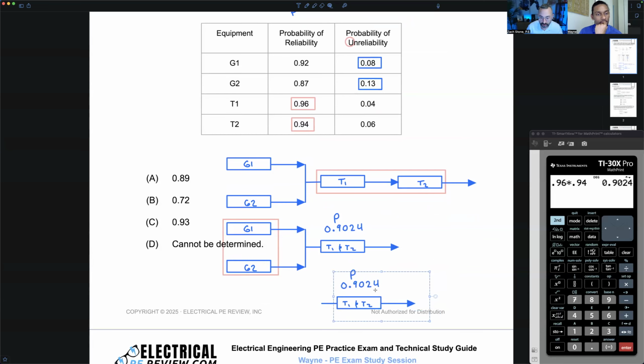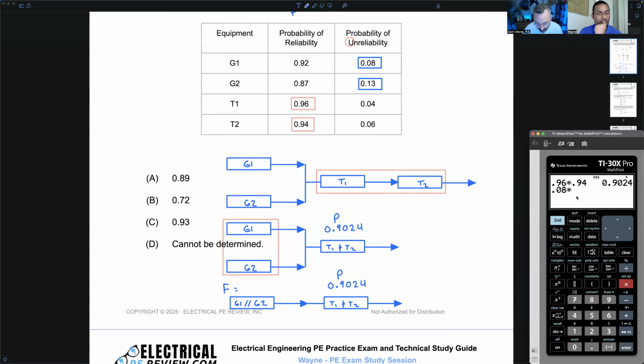So that's going to look like this—here's our transformer, and this is like G1 in parallel with G2. Their probability of unreliability: we multiply 0.08 times 0.13. That gives us, again, not a probability of reliability, but a probability of failure or unreliability for both generators. It comes out to 0.0104. Are you with me so far? Yes.